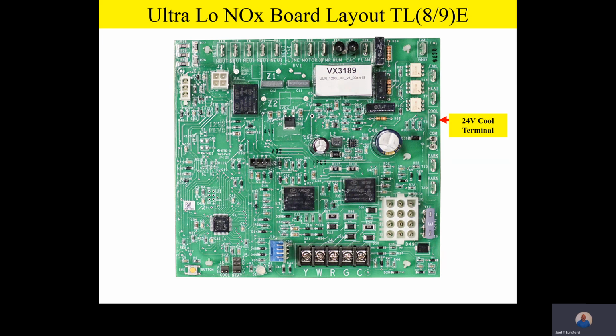So again, this cooling tap will be energized anytime you have a Y call to the board, and again, we're going to manipulate this cool tap for 65% airflow when we start talking about a two-stage product and our Y1 airflow. Here we have a 24-volt common to the motor. And again, team, remember, on an ECM motor, you have power to it all the time, and you're going to tell that motor what to do with 24-volt outputs from this board and the thermostat. So there's the 24-volt common to the motor.